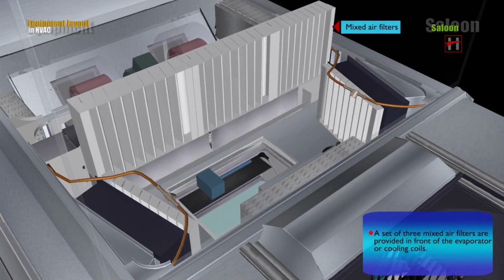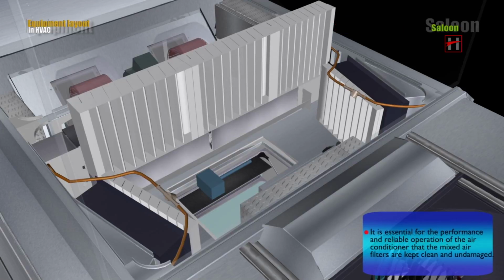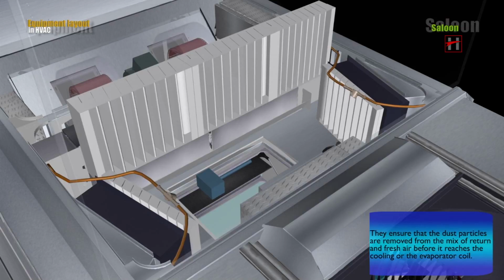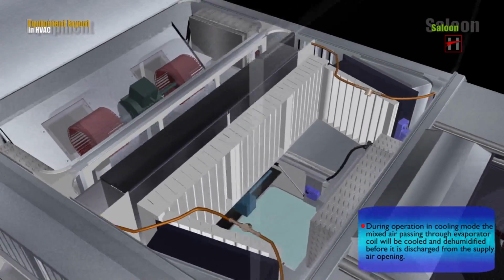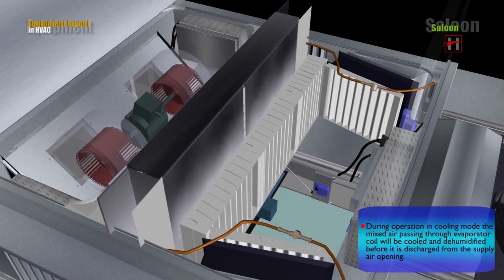A set of three mixed air filters are provided in front of the evaporator or cooling coil. It is essential for the performance and reliable operation of the air conditioner that the mixed air filters are kept clean and undamaged. They ensure that the dust particles are removed from the mix of return and fresh air before it reaches the cooling or the evaporator coil. During operation in the cooling mode, the mixed air passing through the evaporator coil will be cooled and dehumidified before it is discharged from the supply air opening.